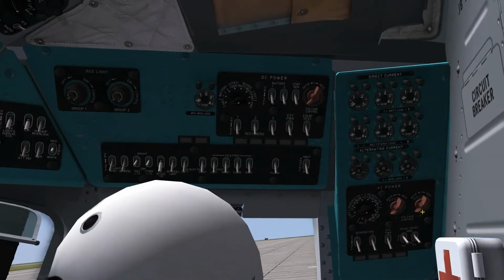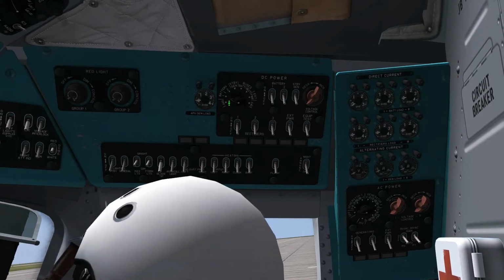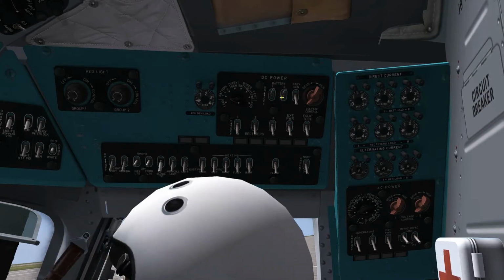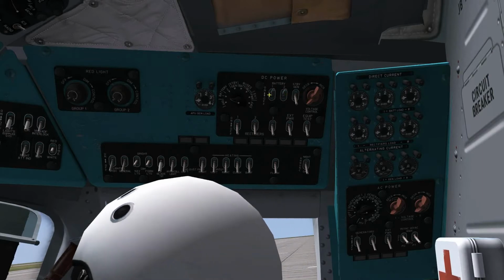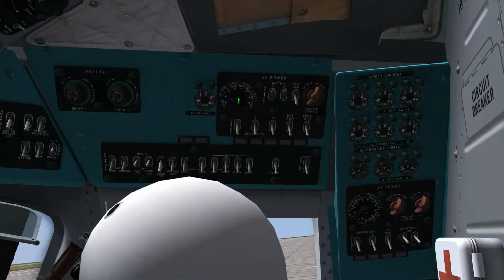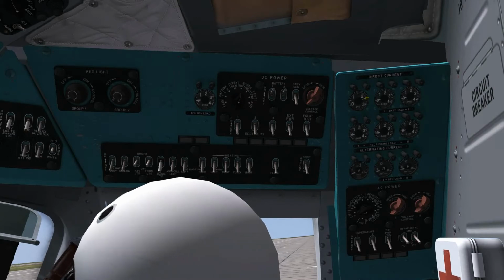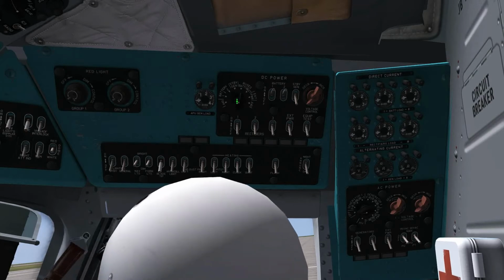So that's good. Now what we're going to do is check our battery voltage, to make sure we have battery power and voltage. You can do this with this switch here. We're going to turn both of them on, and this gives DC power to the battery bus. You can check this meter, controlled by this switch. If we turn the DC selector switch to the battery bus, we can see we've got 24 volts from the batteries. We can also check battery 2 and battery 1 individually, checking the voltage and health of each.